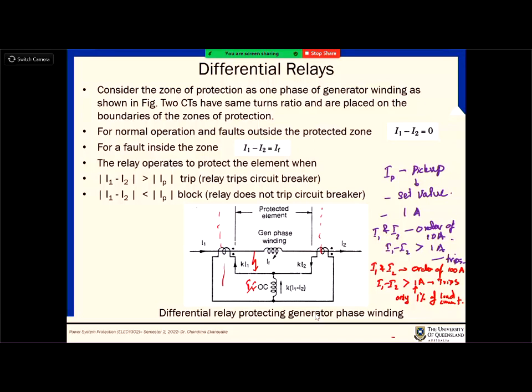But for differential protection schemes, both secondary currents have to be measured as well. How practical is it to have, let's say, a 200 kilometer transmission line where your secondary circuits should be connected? You have to take the secondary current from the other end and this end and then compare. Do you think that is practical? No. You just need fiber optics. Yeah, you could send the signals there easily. Even without fiber optics, if you have microwave links, right? That's how they do it.